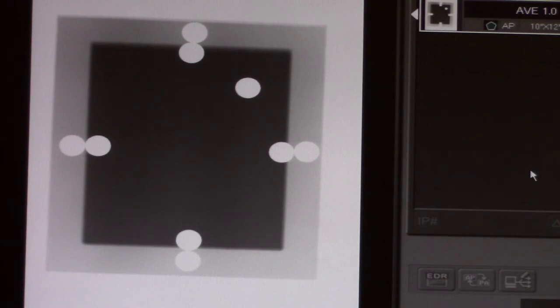Hang on just a second and we're going to have a little bit more discussion before we wind this up. All right, so what have we learned? We're allowed to be off by two centimeters on any given side. We're allowed to be off by no more than four centimeters total including all four sides of the collimated field.